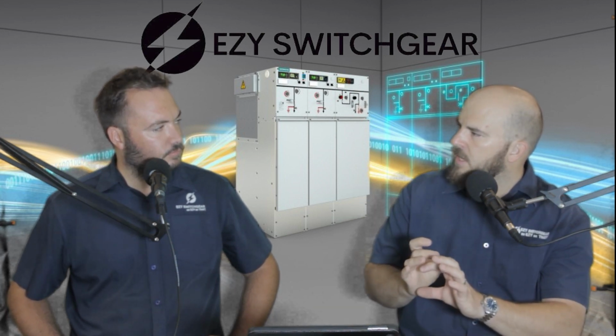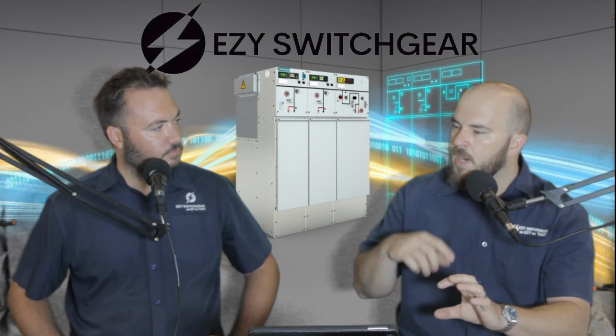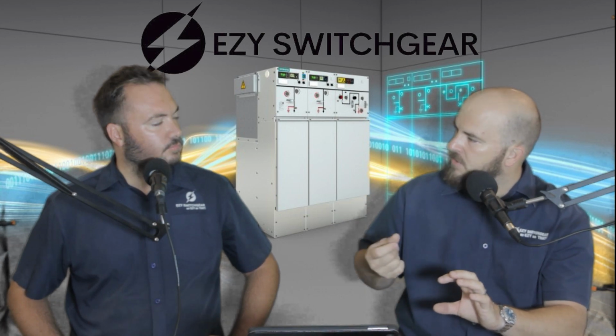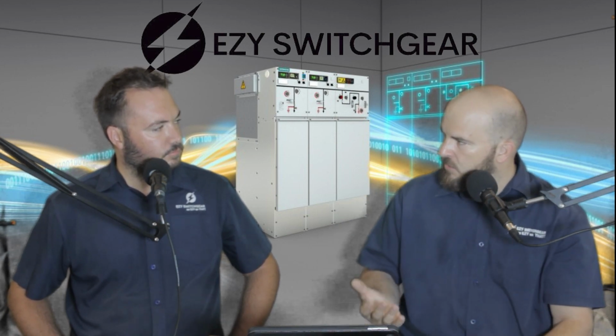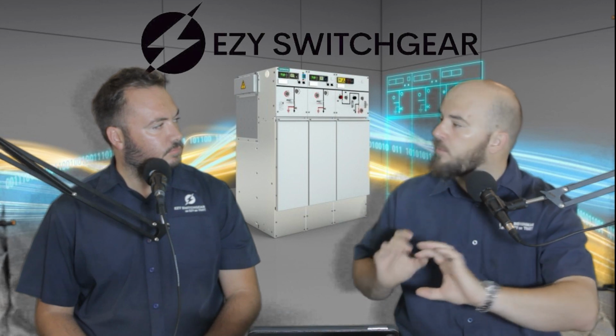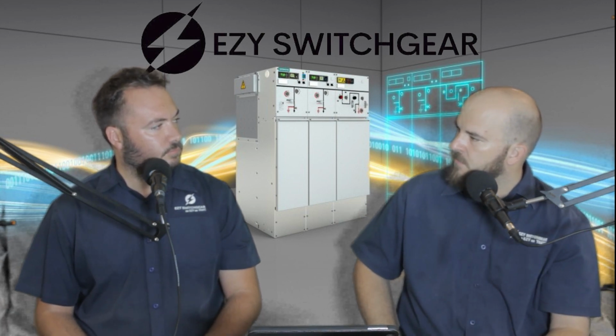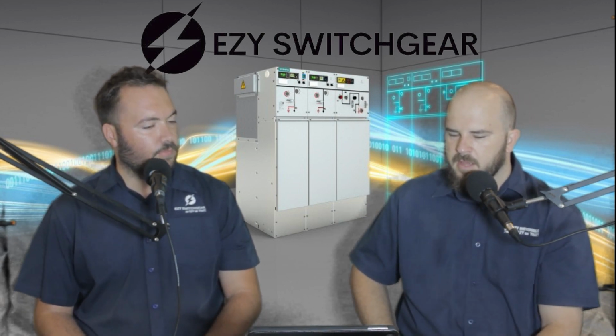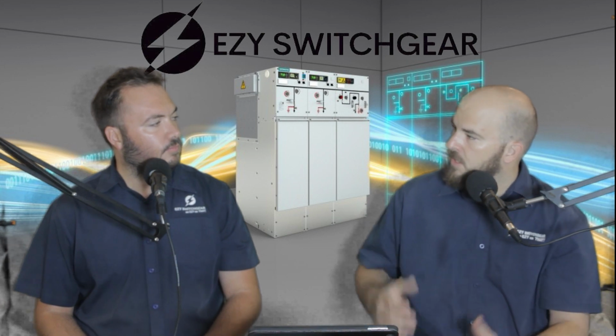So protection has got several roles. When it fails, it will trip out as fast as possible to protect the plant or to protect the human, and then secondly, it will also protect that cable from overheating in the first place, from overcurrent, from pulling too much load. Yes. Okay, great. And even tell us more about the speed and reliability in MV switchgear.